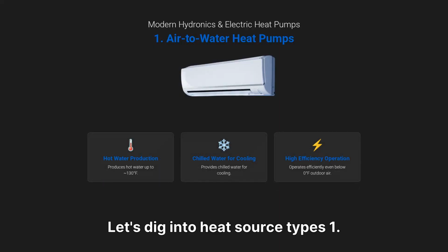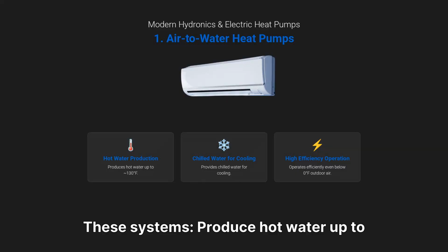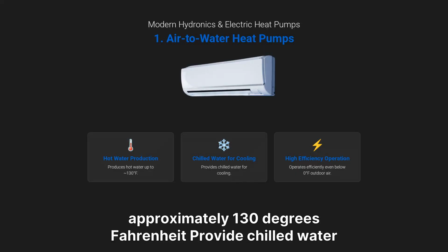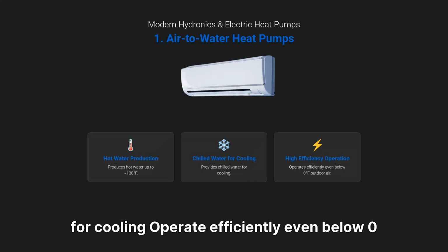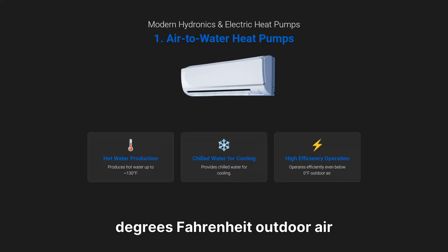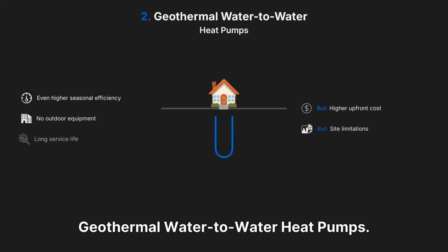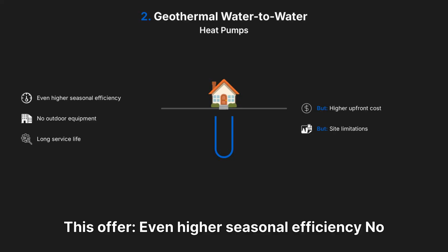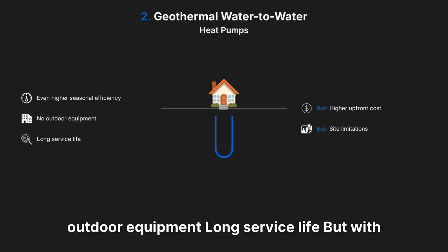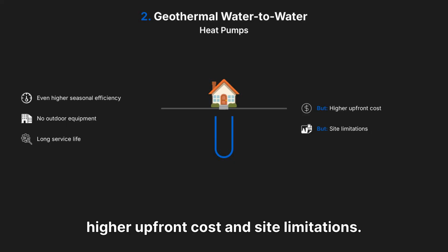Let's dig into heat source types. One, air-to-water heat pumps. These systems produce hot water up to approximately 130 degrees Fahrenheit, provide chilled water for cooling, and operate efficiently even below 0 degrees Fahrenheit outdoor air. Two, geothermal water-to-water heat pumps. These offer even higher seasonal efficiency. No outdoor equipment, long service life, but with higher upfront cost and site limitations.